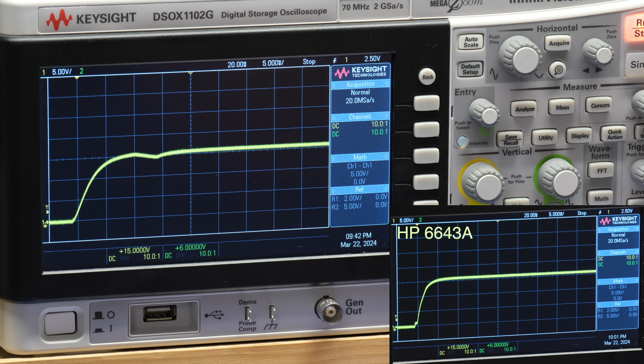I'm measuring the output voltage of the power supply directly at the output terminals, and I have the supply connected to this BK Precision 8600B electronic load. That load will draw 5 amps from the power supply when I turn it on. As you can see on the meter, I have the output voltage set for 20 volts, and the output measures 20.008. Let's turn the load on.